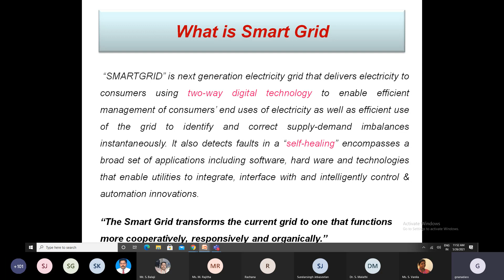As I mentioned, the primary aim of implementing smart grid at the distribution side is to reduce aggregated technical and commercial losses, increase grid stability, and carry out peak load management, since power demand is very high during peak load conditions. Transformers are designed according to that. For example, if our feeder consumes 10 megawatts normally, but during peak load periods of morning and evening it consumes 14 megawatts, then the transformers are designed for 14 megawatts.